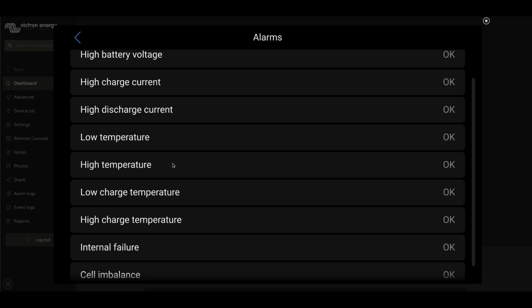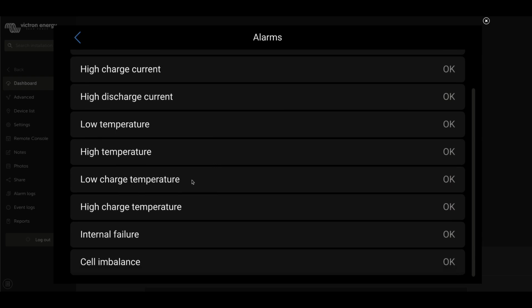Low temperature, high temperature, fairly obvious. Low charge temperature, high charge temperature. These are a note that will come up if, for example, it's very cold, you'll end up having a difficult time charging. So if the battery bank is usually below around 40 degrees Fahrenheit, you might start to see some low charge temperature alarms. The cell imbalance is an indication that either a battery is isolating itself or a cell is failing or some other system like that.